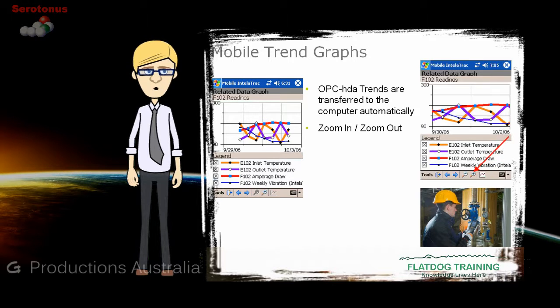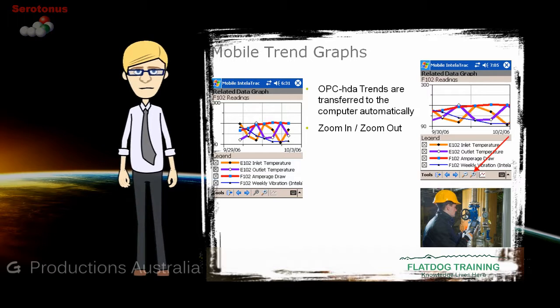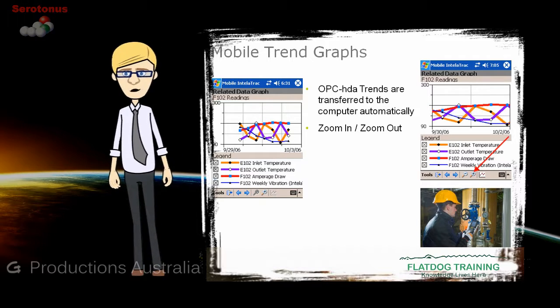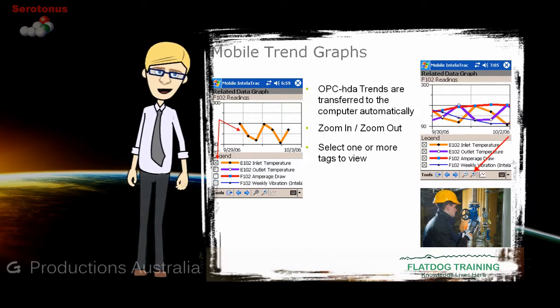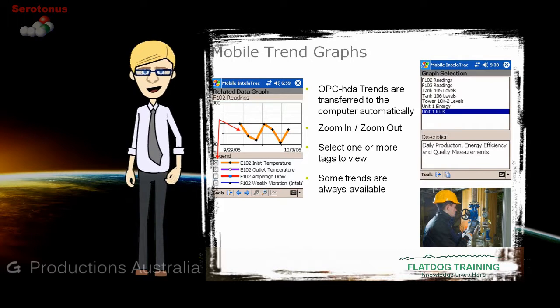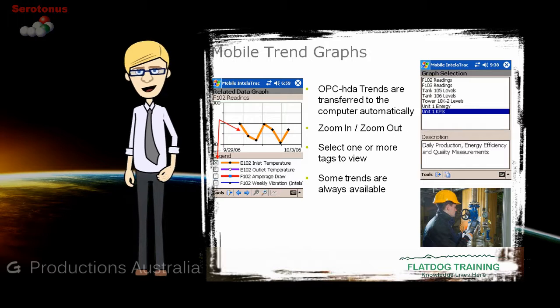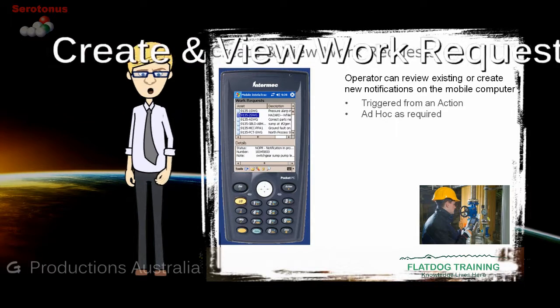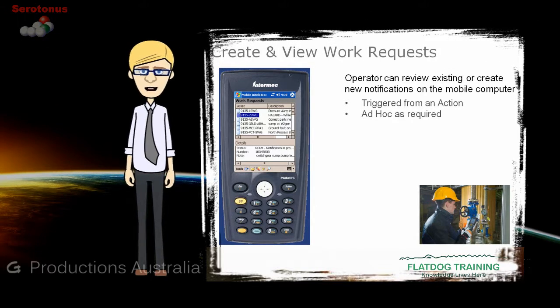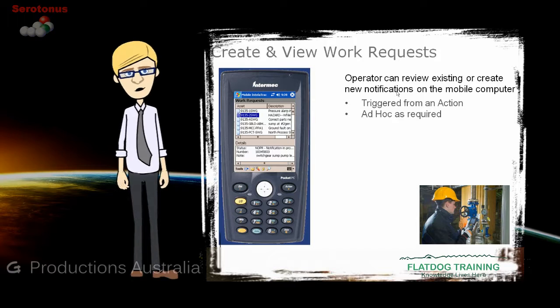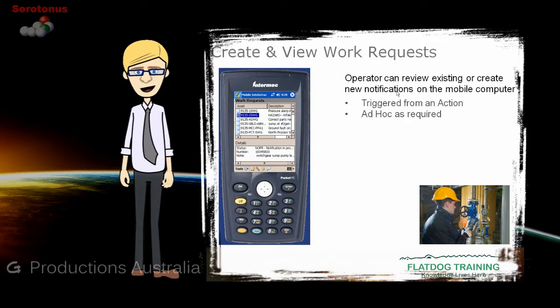I can zoom in and zoom out on my trend, get more detailed information, and I can select one or more tags to view in my trend. Some trends are always available, and some are available on that particular procedure when needed. I can create and view work requests on my handheld, and can review existing or create new notifications on the mobile computer. This can be triggered from an action or ad hoc as required.